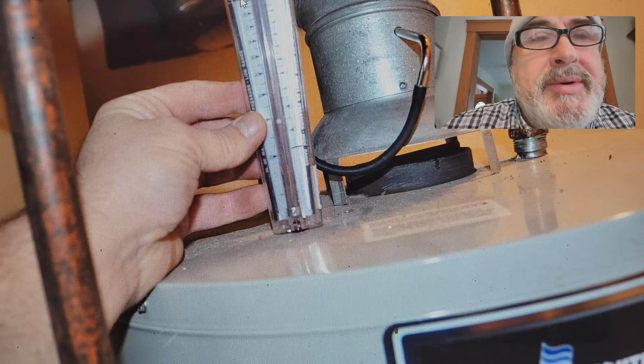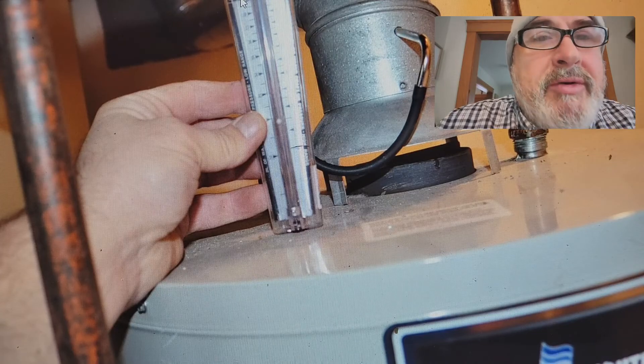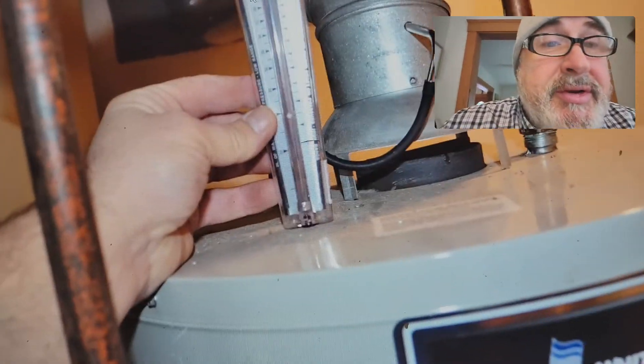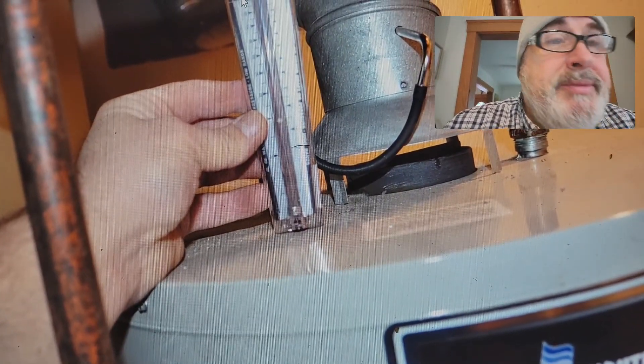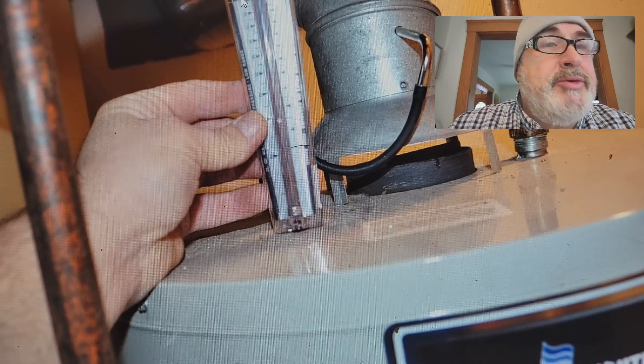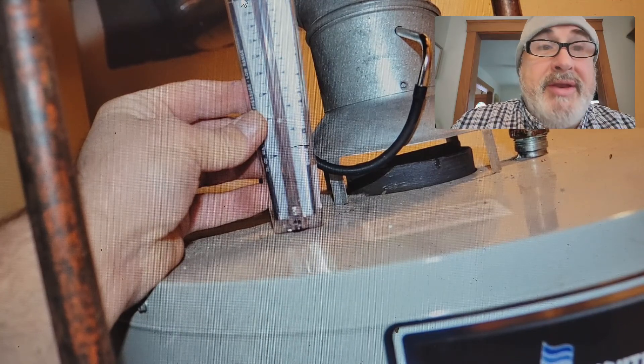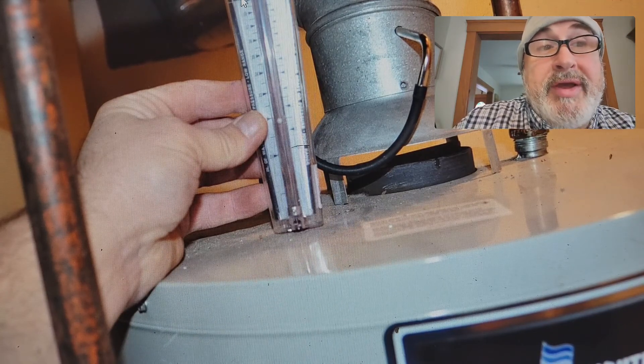Whenever you have a gas fire system, you have what's called a stack effect. The hot air is going to go up the flue. Now, if the flue is restricted or covered or plugged, or there's an animal in there, or the flue is too short or too long, or there's too much stuff connected into it, then you have poor draft.